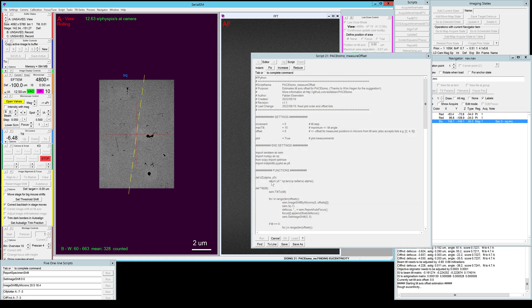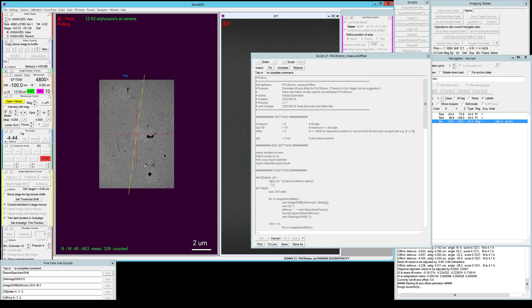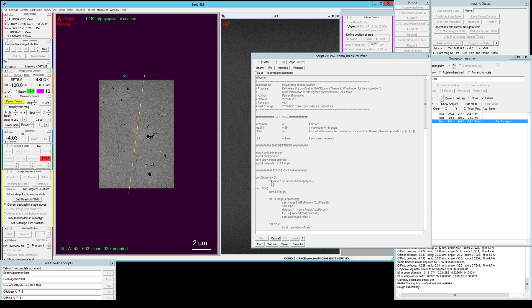What it will do is run three, in this case, different tilt series: plus five microns of the tilt axis and minus five microns of the tilt axis. It will just measure the focus by beam tilt on all these spots, and in the end it will use that to calculate the offset of the tilt axis from the optical axis.